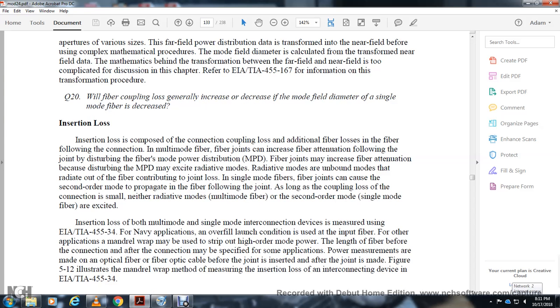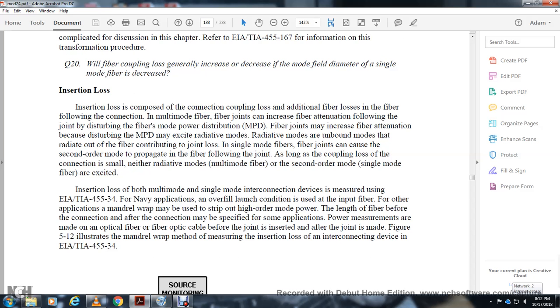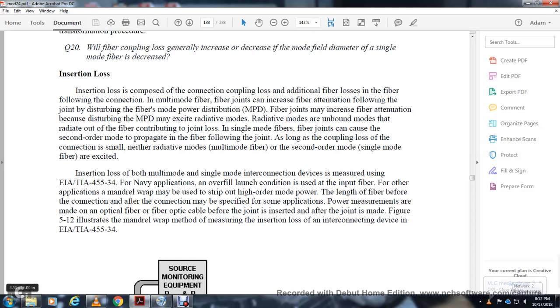Insertion loss is the technique for measuring the attenuation introduced by connecting fiber sections. For multimode fiber junctions, the fiber attenuation following a connection depends on the mode power distribution. Fiber joints must recover the bound mode power distribution; modes radiated out of the fiber at the joint result in additional loss. Interconnecting devices are measured using EIA/TIA-455-34. The measurement may use overfill launch conditions or other conditions depending on the application.